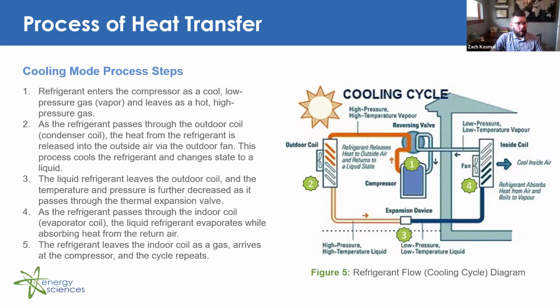If we were in heating mode, this cycle would just reverse itself, in which case that inside coil would become your condensing coil, and the outdoor coil would become your evaporator coil. So it can get a little confusing, especially if you're thinking about an AC unit specifically. We always call those outdoor units for your residential AC units. We call those condensing units, but that verbiage can change depending on heating or cooling cycle in a heat pump.